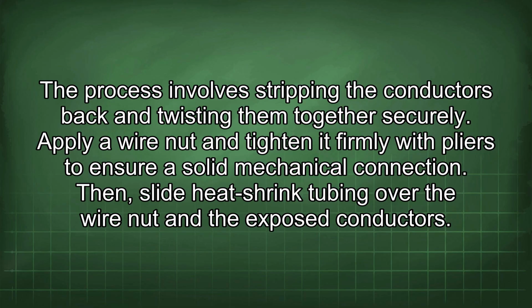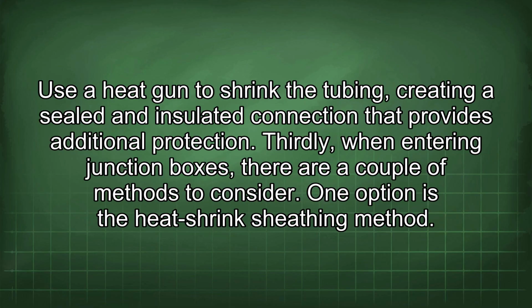Apply a wire nut and tighten it firmly with pliers to ensure a solid mechanical connection. Then slide heat shrink tubing over the wire nut and the exposed conductors. Use a heat gun to shrink the tubing, creating a sealed and insulated connection that provides additional protection. Thirdly, when entering junction boxes, there are a couple of methods to consider.